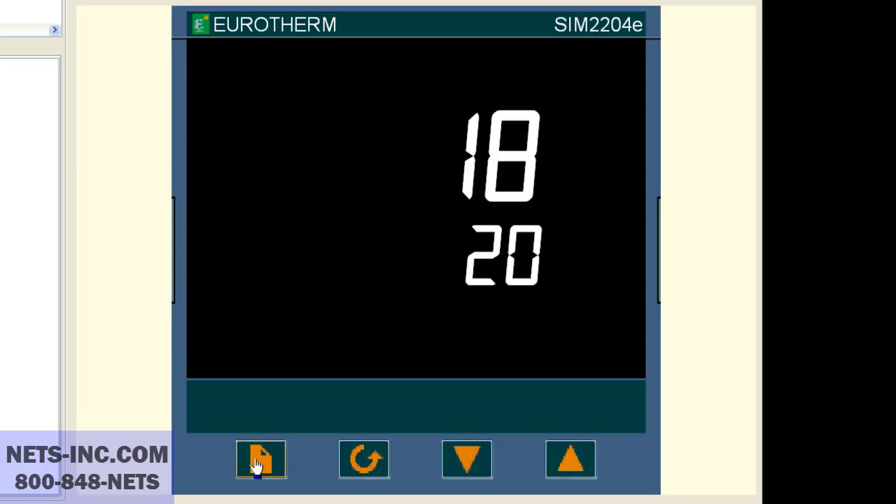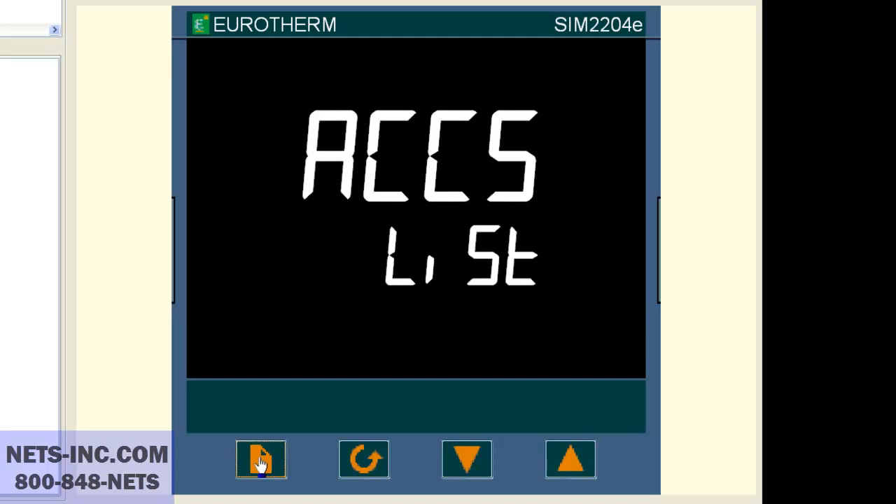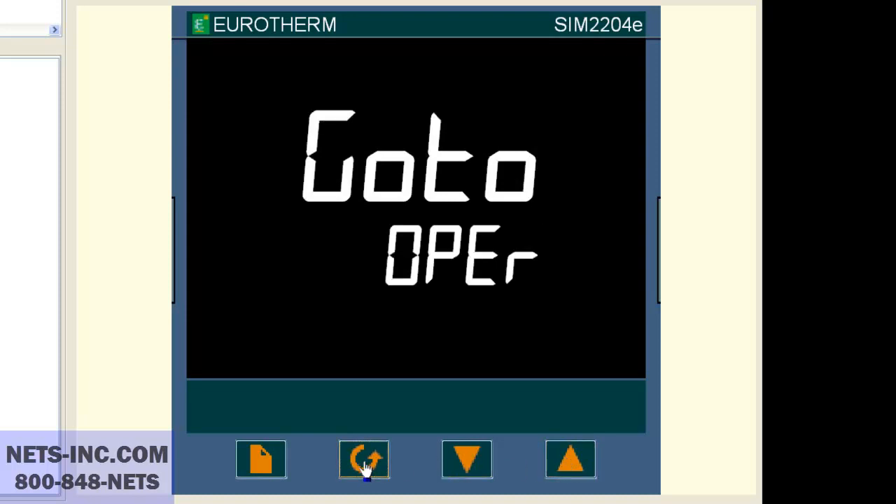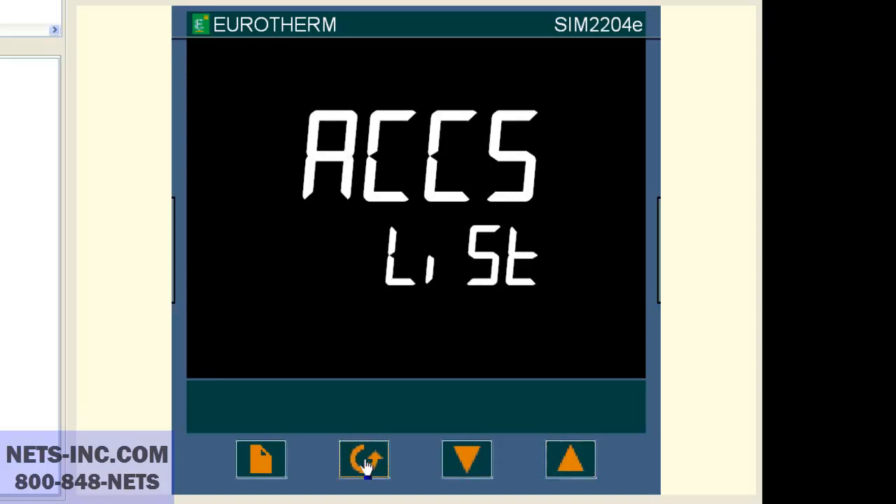If you do not see the SP list, then the list is hidden from the operator. If so, we must put the controller into the full level to see the SP list. To put the controller in full level, press the page button repeatedly until you see an ACCS list. Press the scroll button once and the display will read code pass or code zero. With the up button, change the value to 1. Now press the scroll key once and you will see go to OPER. With the up or down buttons, change the OPER to full. Now press the scroll button once. Press the page button repeatedly until the display reads SP list.